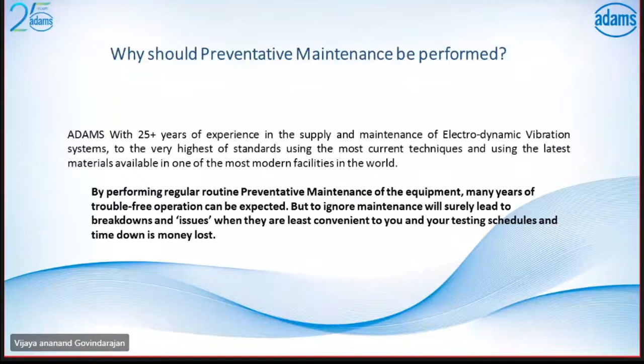The vibration system vibrates the payload for fatigue or destruction tests. This system has many dynamic parts, like in an automobile, comprising flexures, rollers, dust seal, bellows, armature, that is the moving coil, bearing, shaft, suitable bolts, etc. So the resultant vibration force generated is a combination of vibration forces experienced at each of these parts.